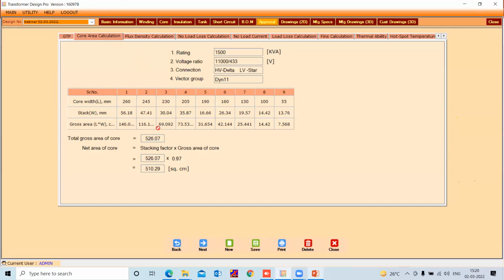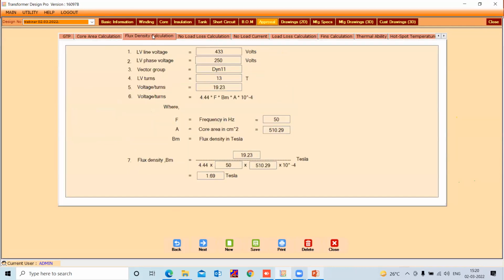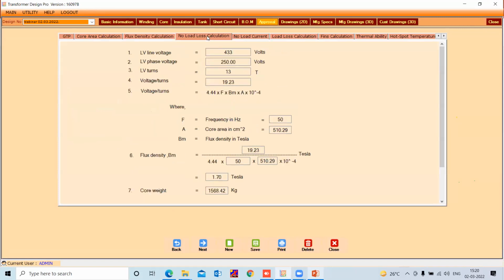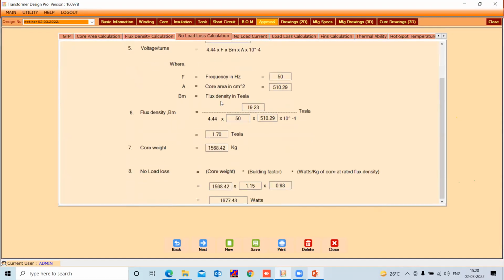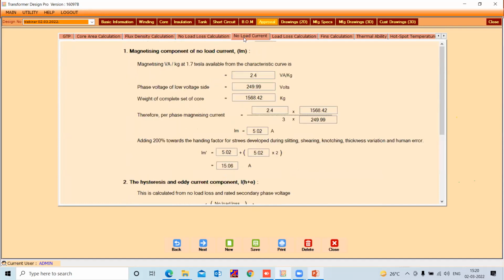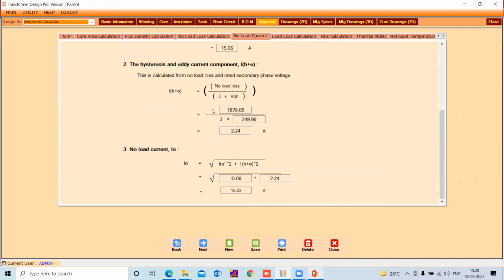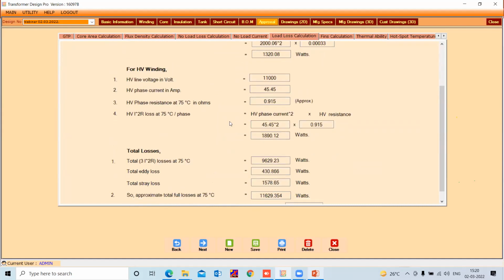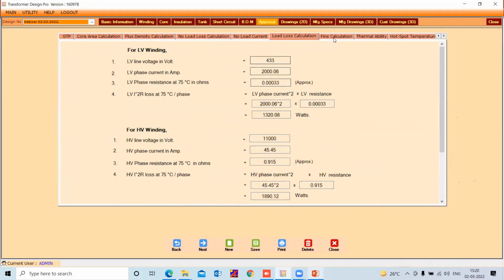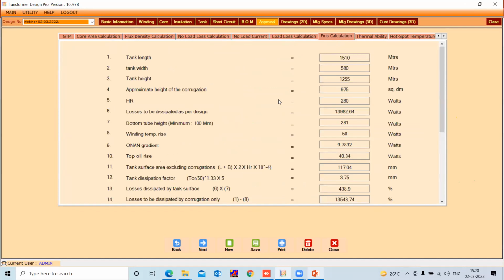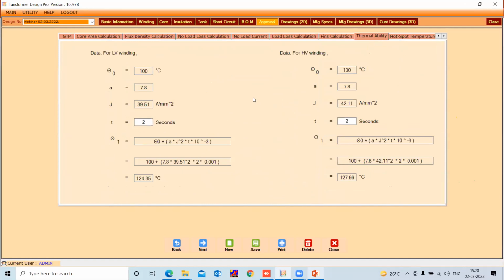So how we calculated core area, that calculation is given here. Then the flux density calculation, then no load loss calculation, then no load current calculation, then load loss calculation, then fins calculation, or you may say heat dissipation calculation, then thermal ability calculation.